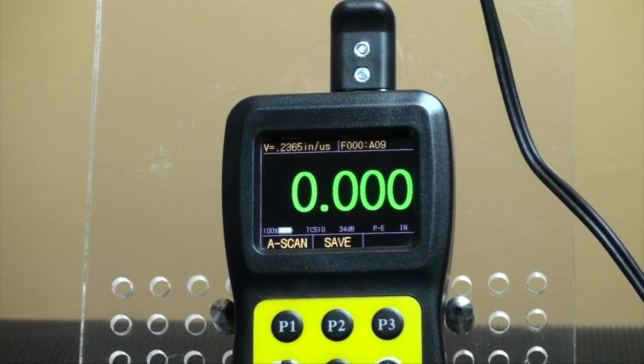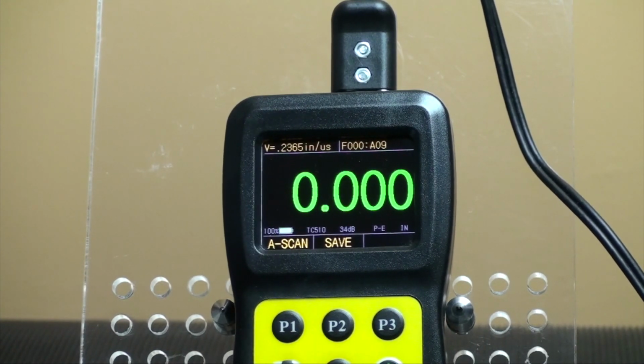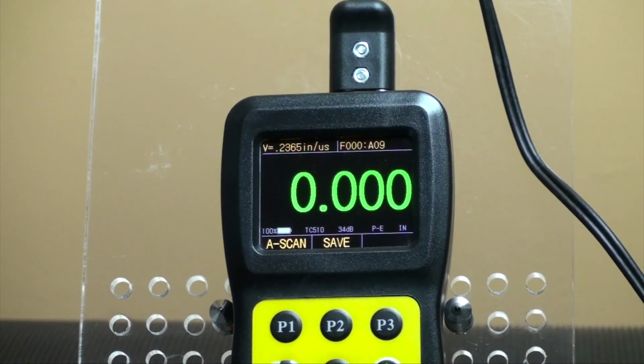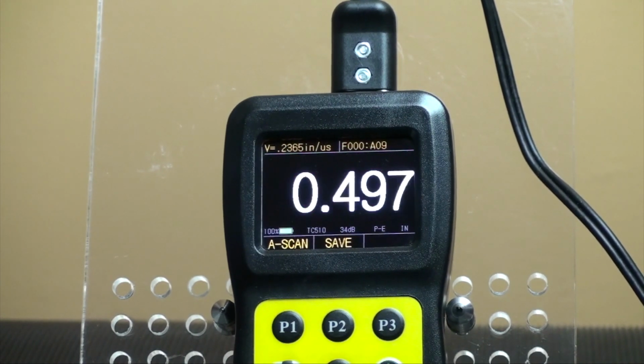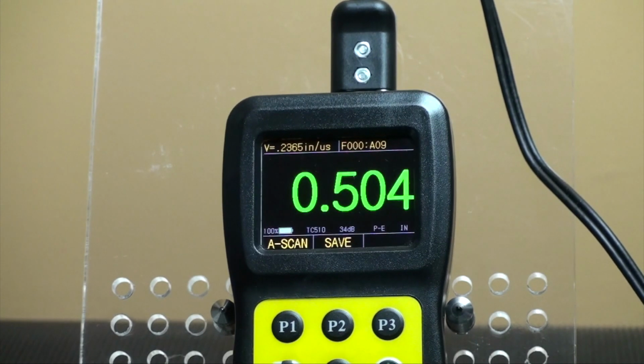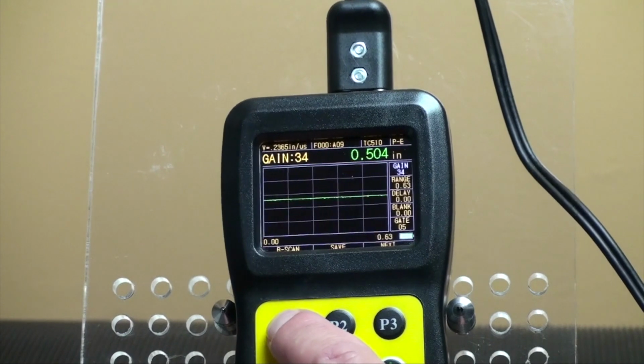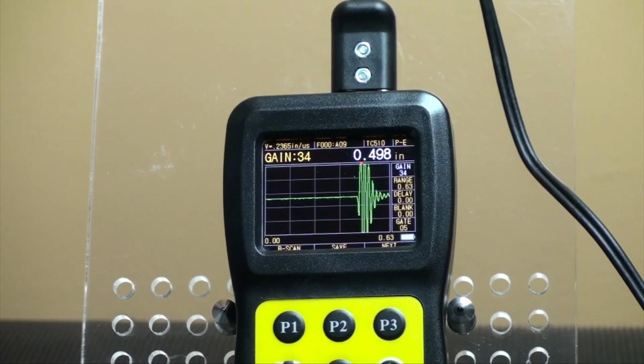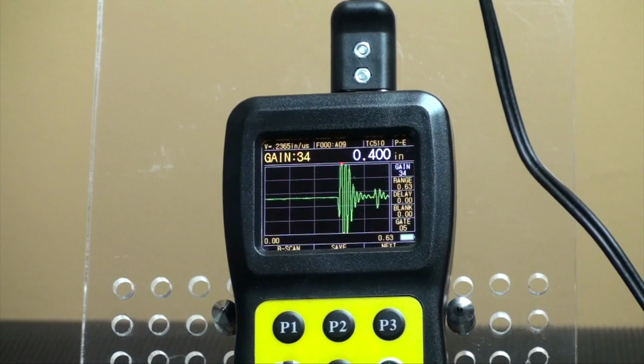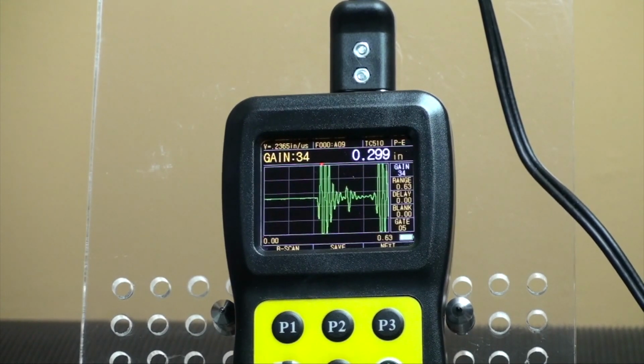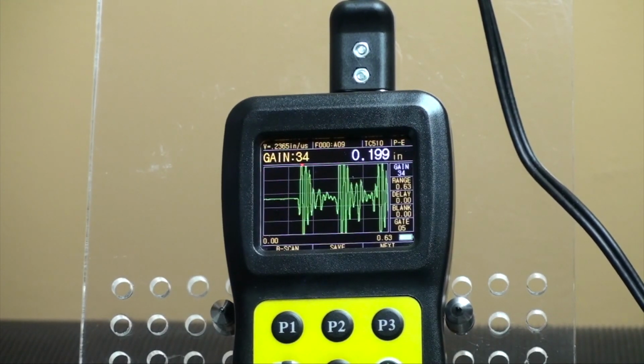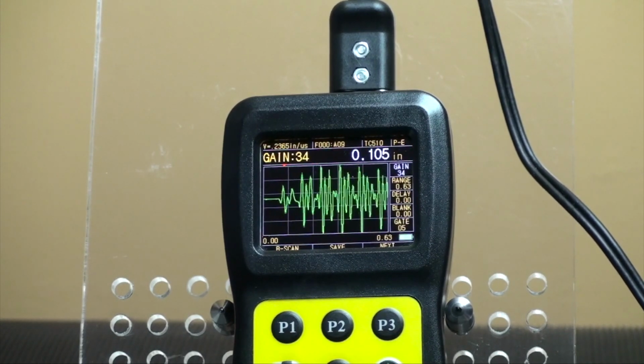The UTG-4000 has 3 different display modes to choose from. Normal mode. This is used to obtain a thickness value of material being tested. In this mode, the interface will show the thickness of the material, sound velocity, and the unit. The A-scan mode. This interface allows you to see the present thickness value and the A-scan waveform at the same time. The right side of the interface is the specification adjusting area, which can be adjusted for a more precise result.